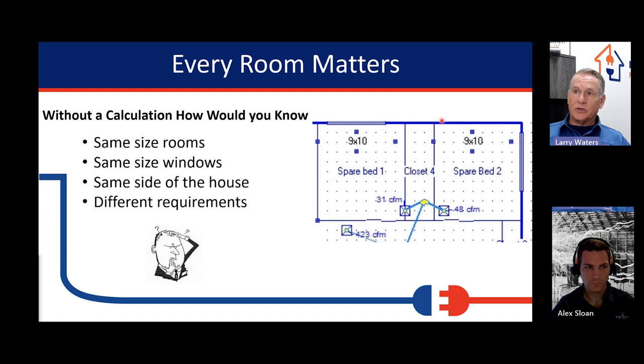If we understand, it's got 2 areas of influence. Mother Nature is acting on 2 sides of this room. So every house that has a corner bedroom needs more airflow than the bedroom next to it that only has 1 wall. You can just know that. Is it enough to change duct sizes? No. The same size duct went to both these rooms. We just had to put a damper on and damp it down. But this is not always done.